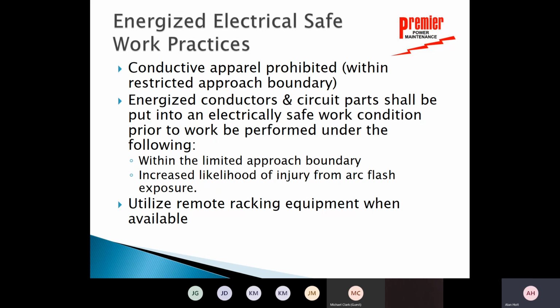Or, in addition to that, if there's an increased likelihood of injury from an arc flash exposure. This one's always been crazy to me. It is a statement made in NFPA 70E, but why in the world would I want to work around anything when there's an increased risk of injury or exposure? I've got enough problems in my life without taking additional risks, so we don't want to do that. We are told Marathon spends a lot of money on remote racking equipment, and that we want to use remote racking equipment when possible.